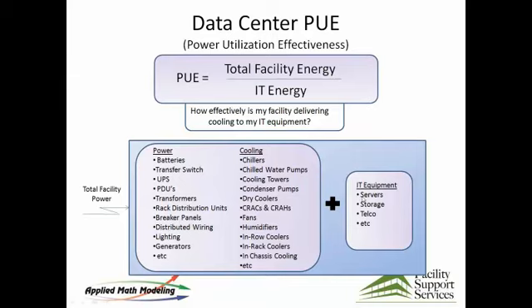So not only do you have the IT equipment that's consuming power, but oftentimes you will get 10–15% over here in just leakage inefficiencies of that. And it's the sum of those two items compared to the IT energy that characterizes your PUE. So a very low PUE is good, and what that means is that this portion of it over here is small compared to the IT equipment.